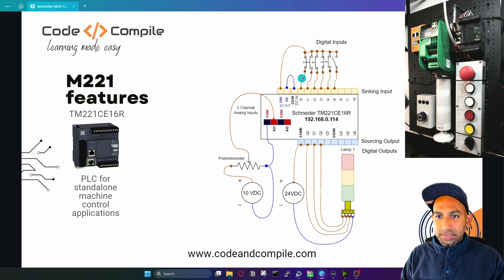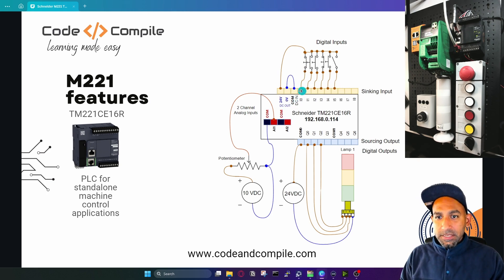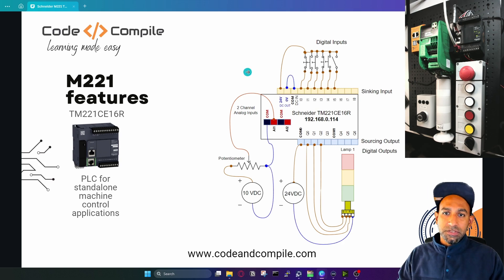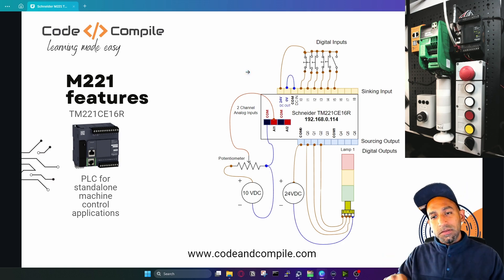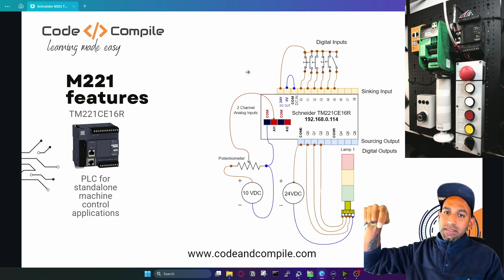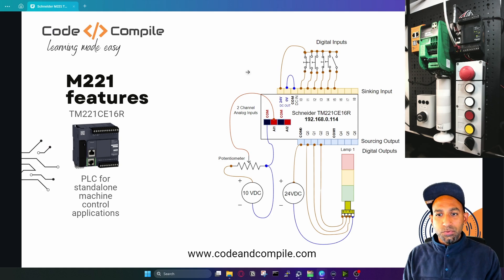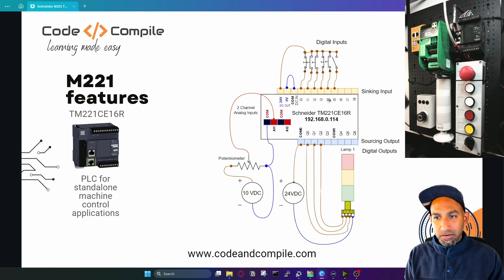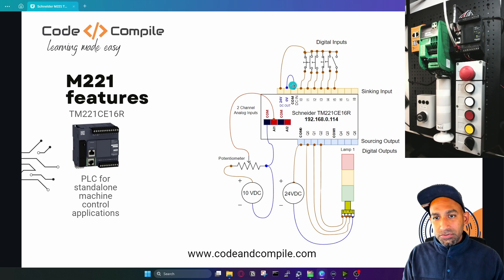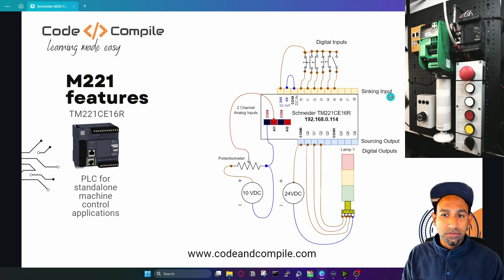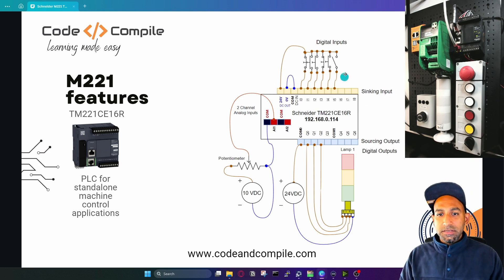Digital inputs supply 24 volts to the PLC because the common of the digital inputs is connected to 0 volts. When 24 volts goes into these inputs, you can see they share a common. To this common we supply zero volt. So when you supply zero volts to the common and 24 volts comes from the inputs, there is a 24 volt potential difference between the common and the input terminals, which triggers the PLC input. If you connect 24 volt to the common and zero volt to the inputs, this will also work — in that case it will be sourcing the input.